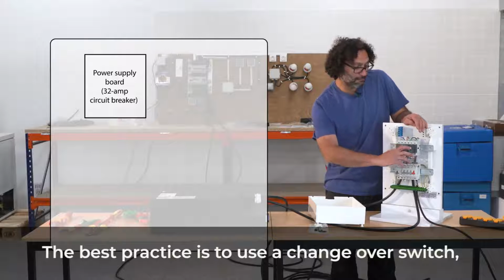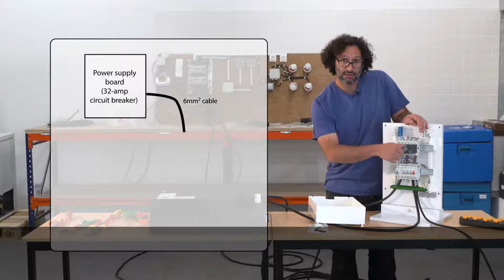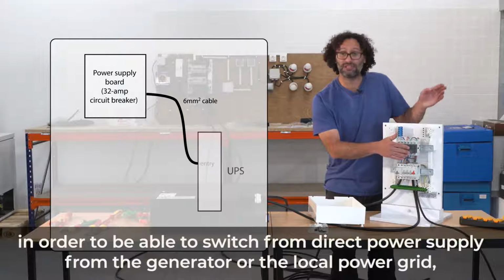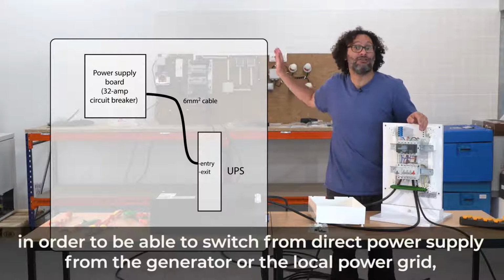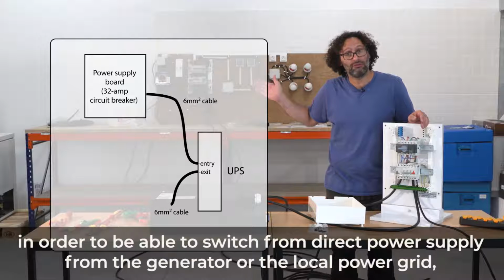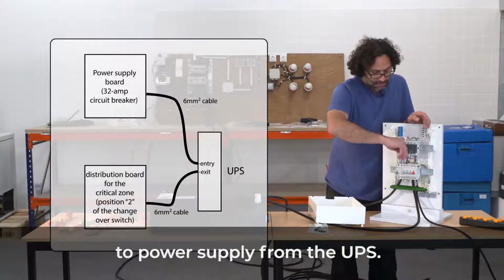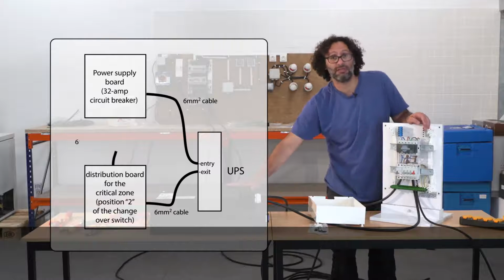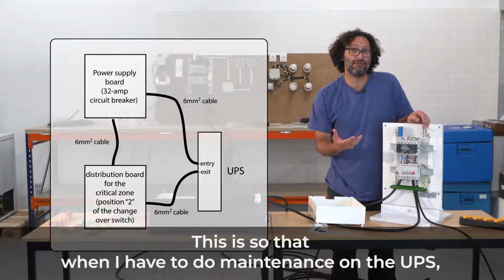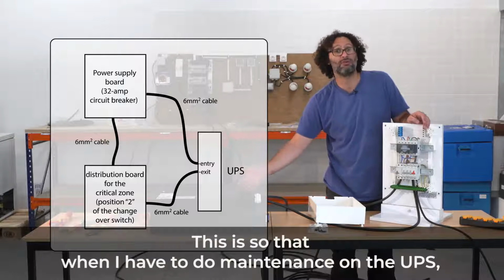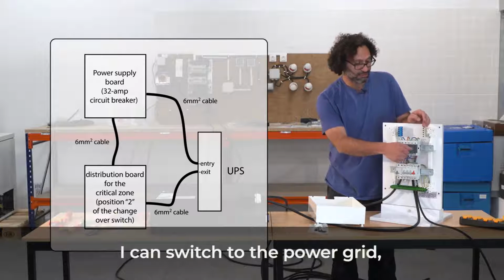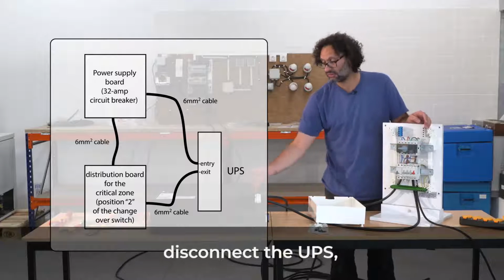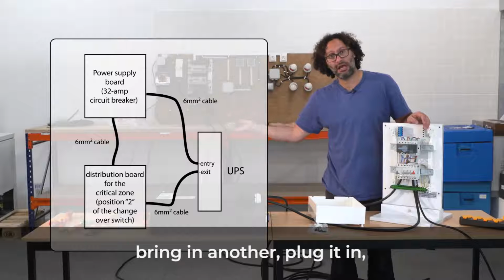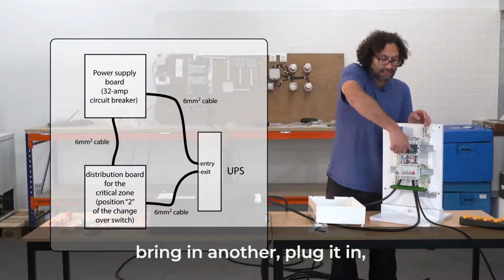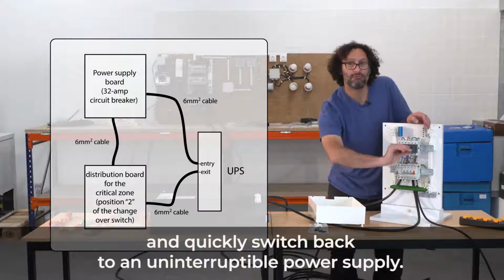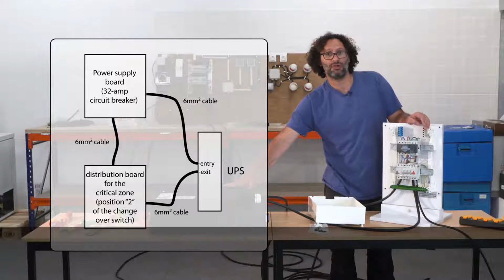The best practice is to use a changeover switch, in order to be able to switch from direct power supply from the generator or the local power grid to power supply from the UPS. This is so that when I have to do maintenance on the UPS, I can switch to the power grid, disconnect the UPS, bring in another, plug it in, and quickly switch back to an uninterruptible power supply.